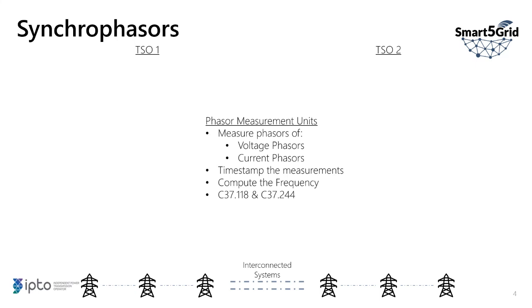The phasor measurement units, PMUs, measure phasors of voltage and current, meaning amplitude and angle of voltage and current. Those measurements are time-stamped and sent to the virtual phasor data concentrators via the IEEE C37.118 protocol, and the VPDCs are implemented based on the IEEE C37.244 protocol. Before sending those timestamped measurements, the PMUs compute the actual frequency of the grid and add this frequency to the data packets.